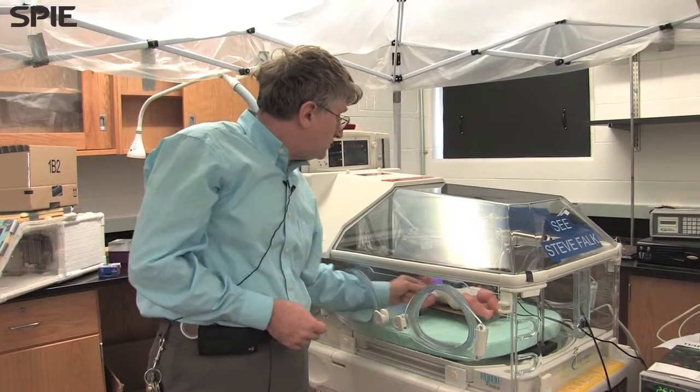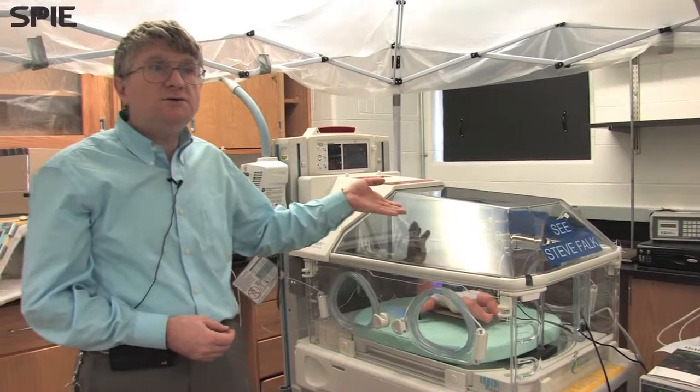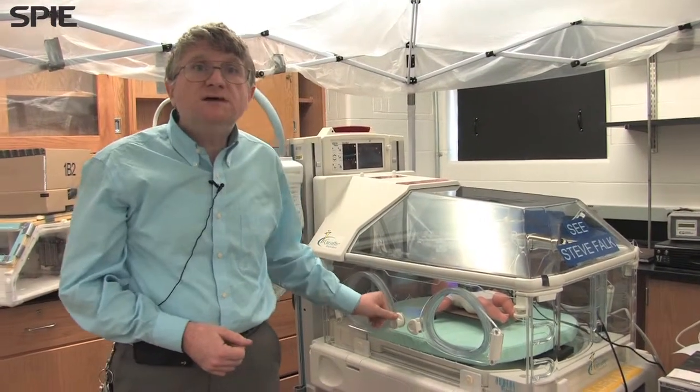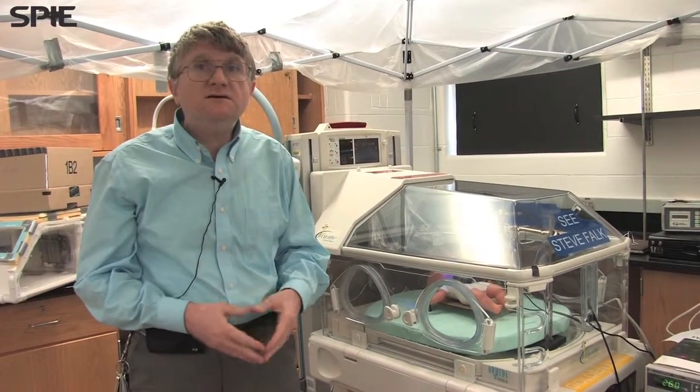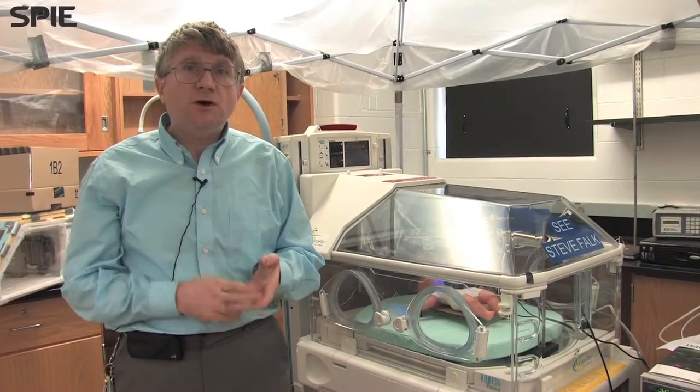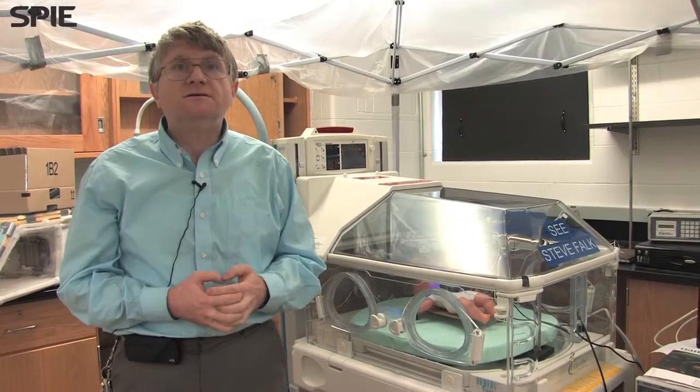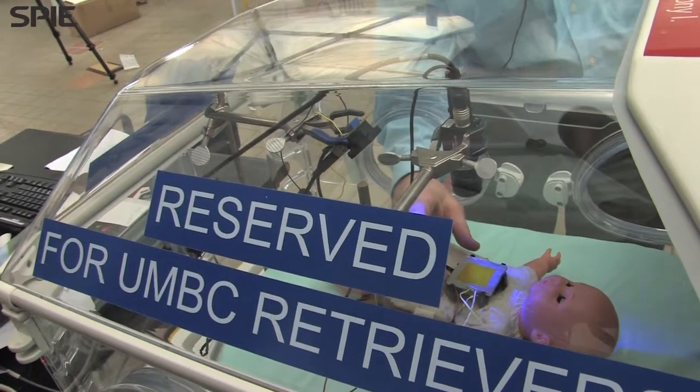You can interrogate it with blue light, which excites the fluorescence of the patch. And you can read it with a camera. The result is you can measure the temperature with exactly the same sensitivity, with exactly the same output rate as the standard sensor, but no injuries, no infections, and no discomfort for the baby.